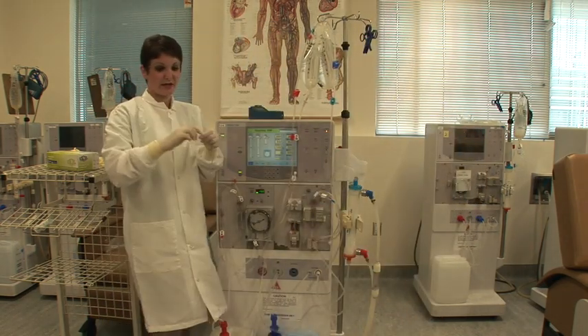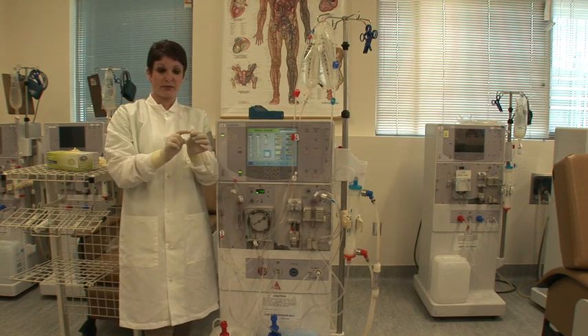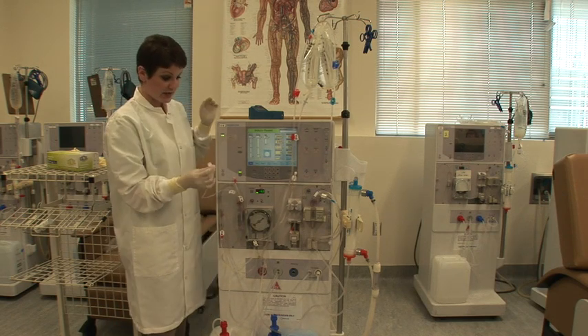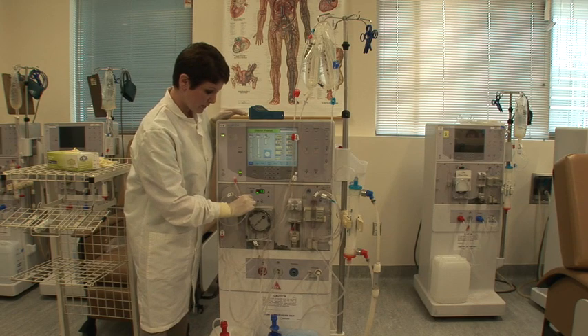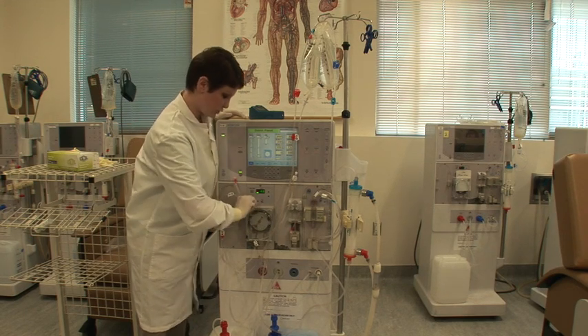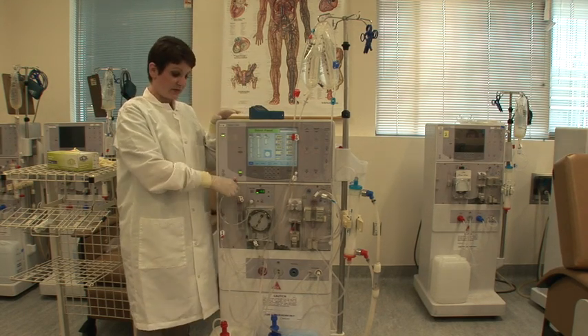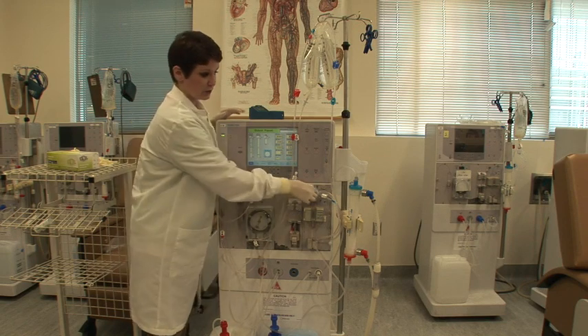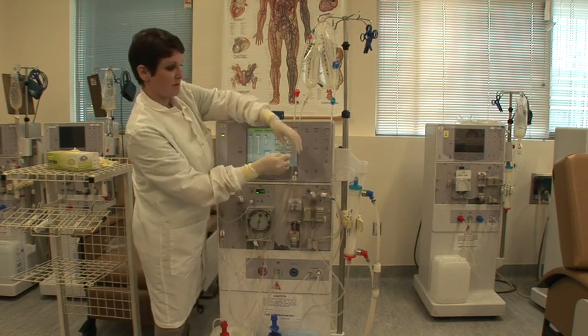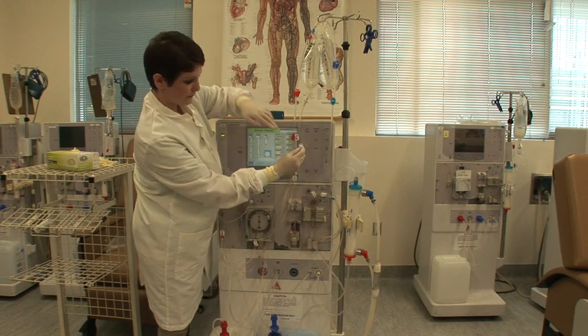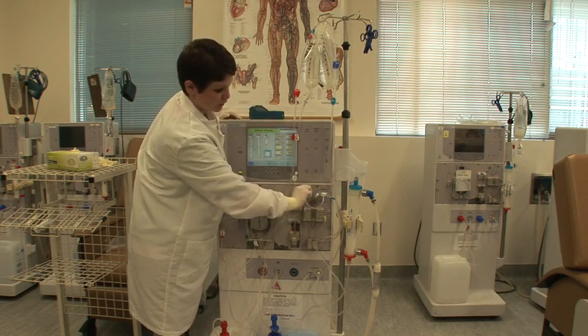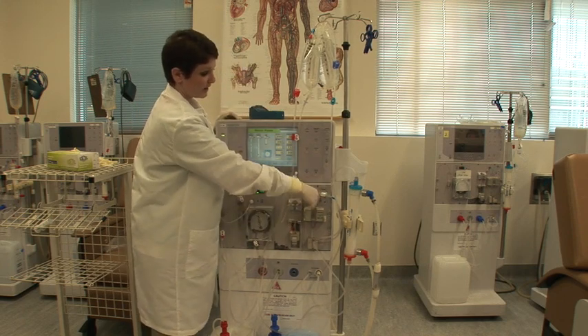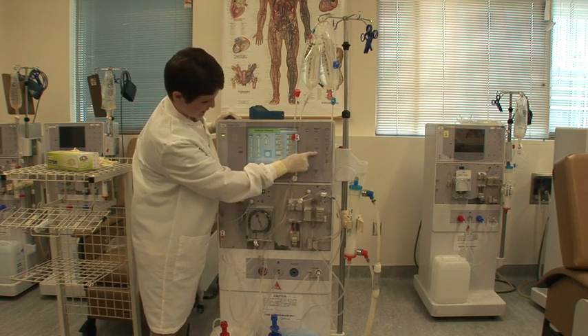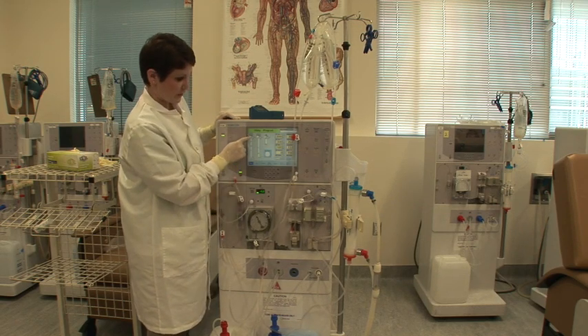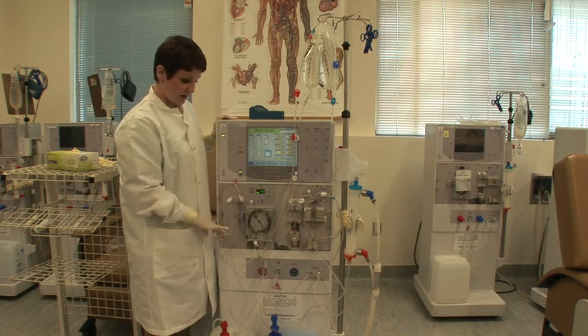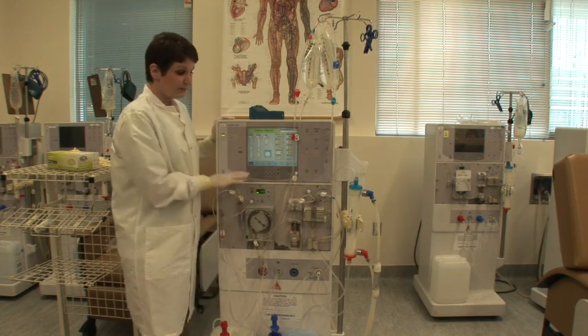Those big long lines, again, make sure that your cap, the transducer protector, is on good and tight. During shipping, they tend to come loose. And you're just going to thread it into the transducer port and then unclamp. You're going to do the same thing on the venous side. Make sure that your cap is good and tight. Connect it to your transducer port and unclamp. Now you will see that we have an arterial and a venous pressure reading. That's coming from these transducer lines.